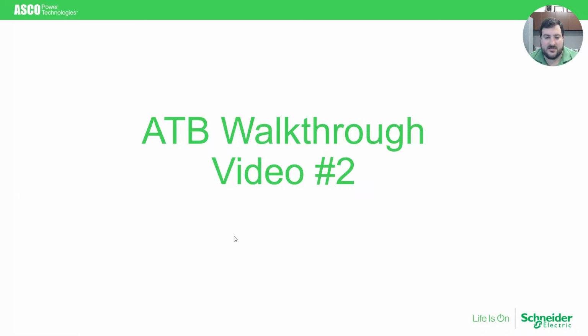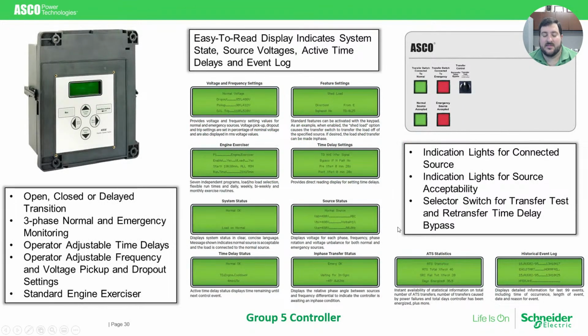But now we're going to move on to talking a little bit more about the controls of a 7000 series transfer switch. The transfer switch, whether it's an ATS or a bypass style, a standard switch or a bypass style switch, is equipped with a controller. And in our products today is the Group 5 controller, which, as I mentioned, serves as the brain of the equipment, taking care of all the monitoring, all the sensing of the voltages and frequency on the equipment, and then using that information to decide what kind of actions to take and whether or not to initiate a transfer.